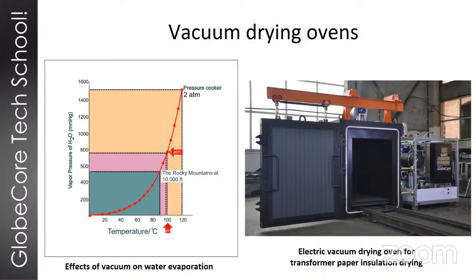Right, so in manufacturing facilities and in repair shops, sometimes what people use are special chambers or ovens, which dry the system not only by heating, but also by vacuum. So the core of the transformer is extracted from the transformer tank. It's installed into this oven, and then it's subjected to heating, which causes water from the insulation to evaporate. And when a certain temperature is achieved, then the vacuum pump kicks in and starts creating vacuum in the chamber to evacuate the water vapor and increase the drying efficiency. And as you can see on this graph on the left of the slide, this is, I'm sure, something everybody knows, that vacuum reduces significantly the boiling point of water. As we can see, we can safely extract water from paper under vacuum with temperature not exceeding 65 degrees Celsius. And this is good for the paper because it does not have the detrimental effects. It does not decompose the paper.